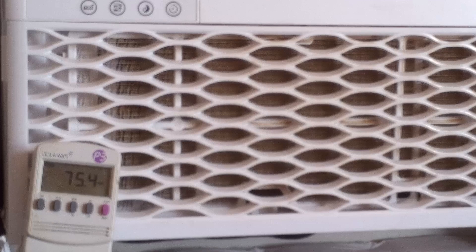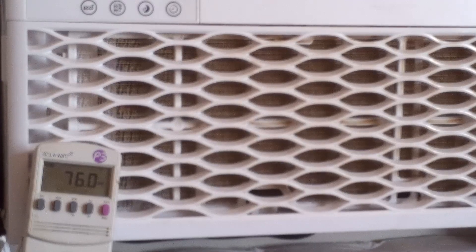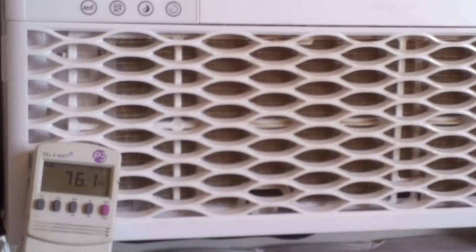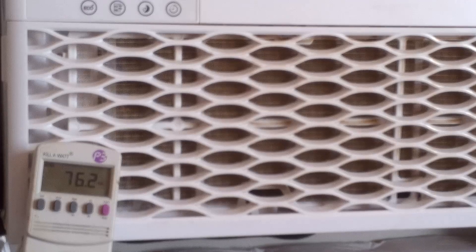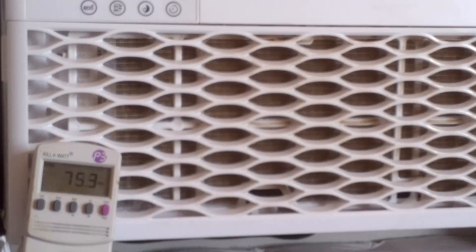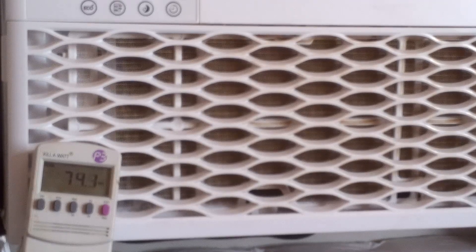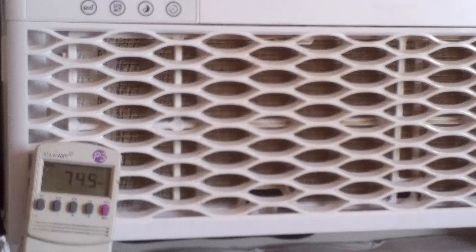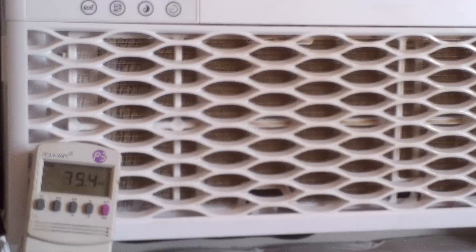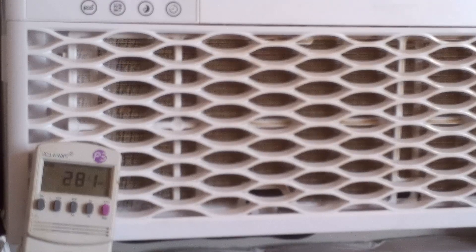When the compressor kicks on, it will probably jump up to about 500 right away and then drop down to 425 and then slowly increase to around 500. Here goes the compressor.